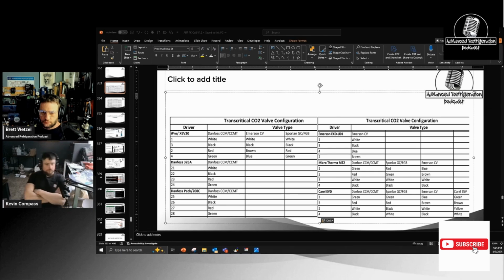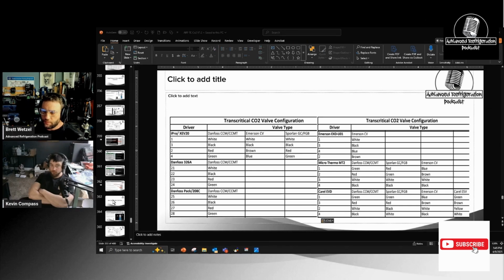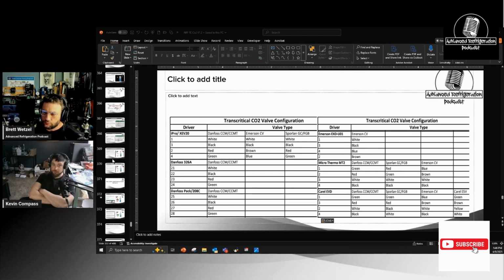And then same things. If you have high subcooling and you have higher than normal pressure and you have high valve percentage, more than likely you're backing up in the gas cooler. Now, there are other things that could cause this. You could have a higher than normal receiver pressure, and that valve is backing off to protect the receiver. You could have a receiver issue. I've seen multiple flash tank valves cause high pressure valve issues. Yes, let me show you that real quick.